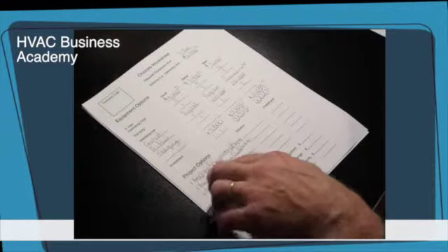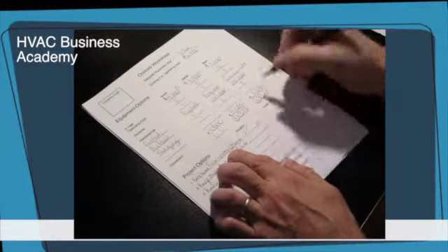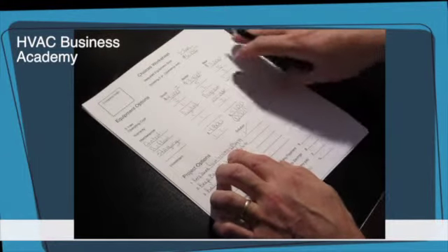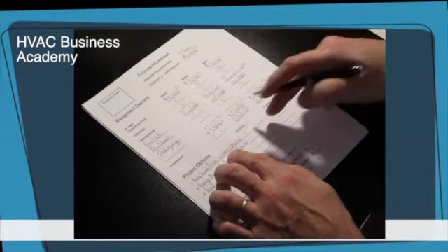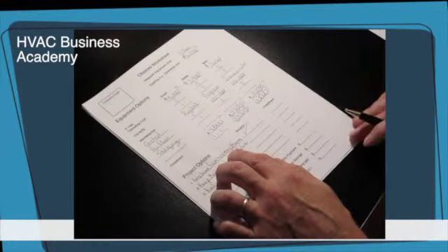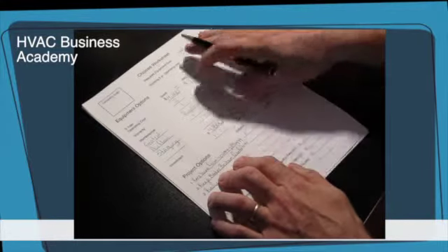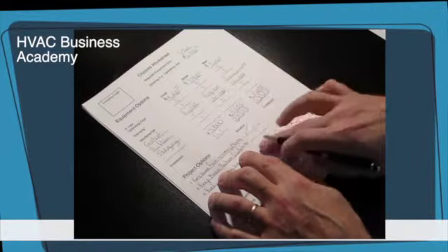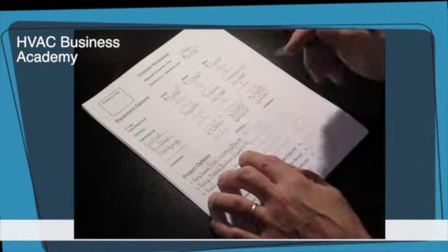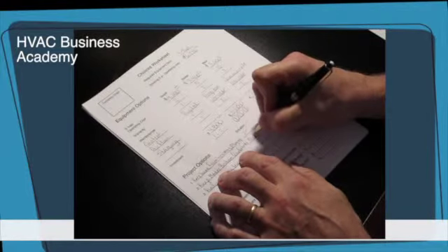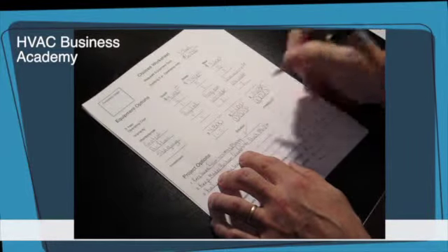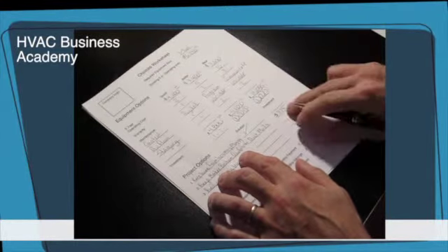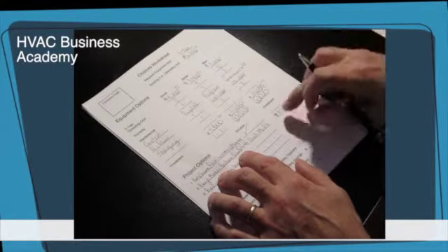All right. Now, to keep the home from becoming muggy, problem solved with the systems that she's selecting. So that's fantastic. No matter what she does, we're going to make a significant improvement and satisfy the first thing on our list. That's great. Keeping the master bedroom comfortable, this will make a significant improvement, but I took some photographs, and what we're going to have to do is increase the duct size to that room because it's just too small and it's far away. So I'm going to put ductwork modifications, duct mods, and that goes for $375. It's something that we can do now to finish the job or later on when she's ready.